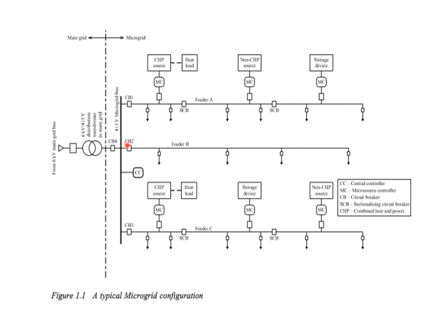The microgrid is coupled with the main medium voltage utility grid through the point of common coupling circuit breaker CB4 as per standard interface regulation. Circuit breaker CB4 is operated to connect and disconnect the entire microgrid from the main grid as per the selected mode of operation. Feeder A, feeder B and feeder C can however be connected and disconnected by operating breakers CB1, CB2 and CB3 respectively. The micro sources on feeders A and C are placed quite apart from the microgrid bus to ensure reduction in line losses, good voltage profile and optimal use of waste heat. Although the control of power flow and voltage profile along radial feeders is quite complicated when several micro sources are connected to a common radial feeder and not to a common generator bus, this configuration is necessary to avail the plug and play feature of the micro sources.